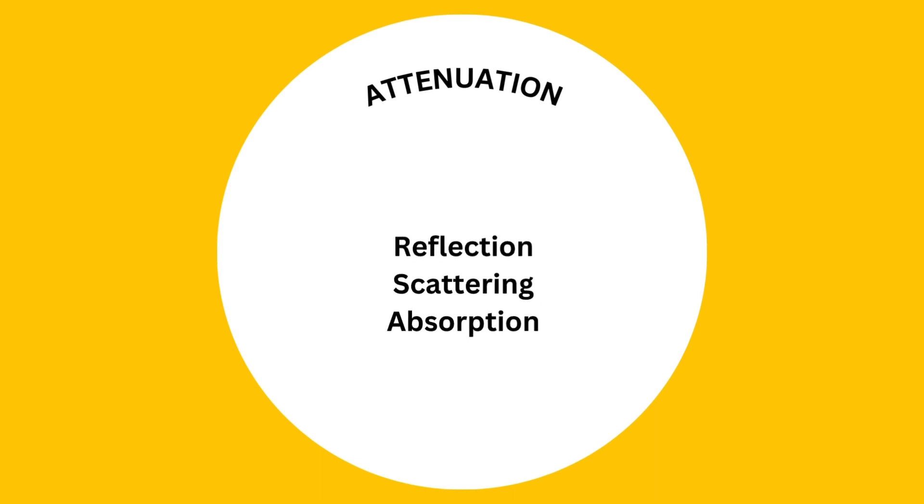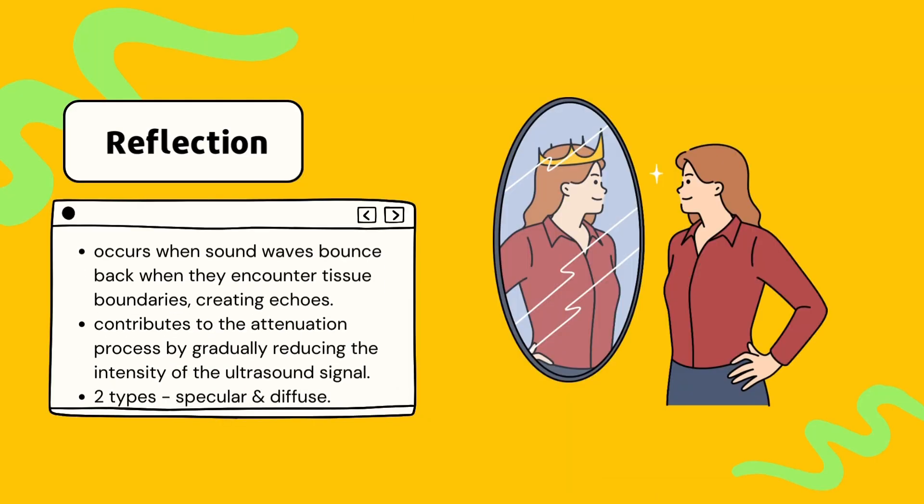As we explore the concept of attenuation in ultrasound imaging, we need to understand the three processes that contribute to this phenomenon: reflection, scattering and absorption. Let's begin with reflection. Reflection occurs when sound waves strike a boundary and some of its energy is reflected back through the ultrasound system.